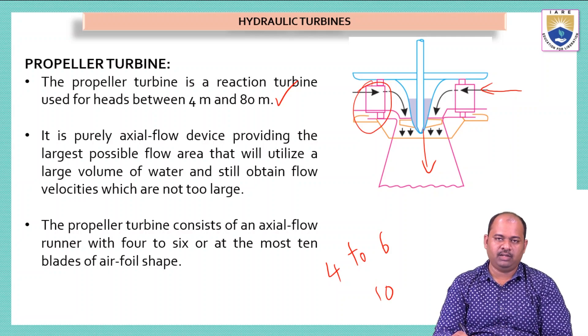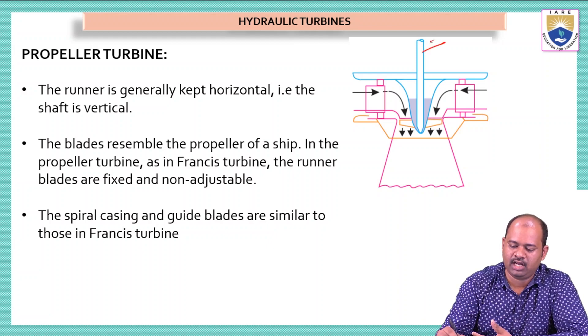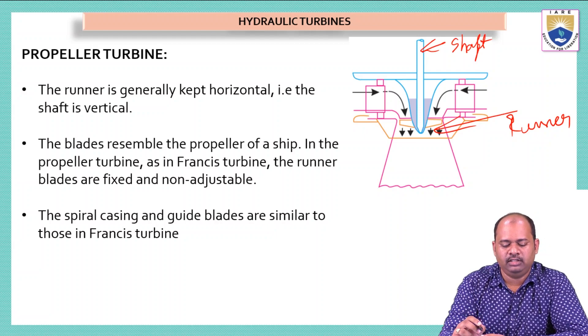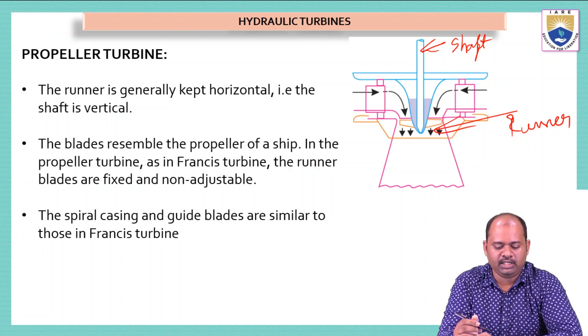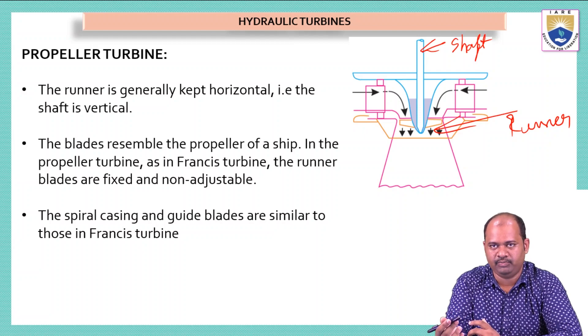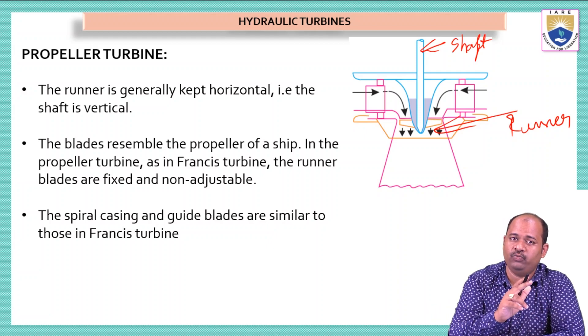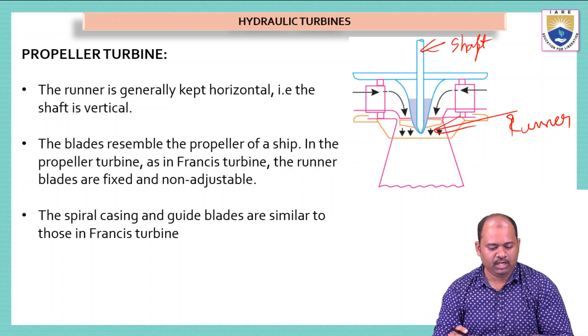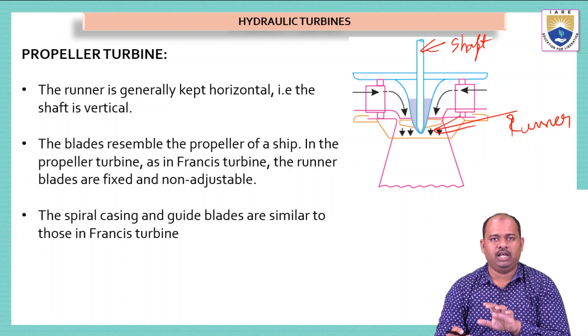The propeller turbine is very similar to the Kaplan turbine, which we will see in the next lecture. The runner is generally kept horizontal with a vertical shaft. The blades resemble the propeller of a ship. In the propeller turbine, as in Francis turbine, the runner blades are fixed and non-adjustable — unlike the guide vanes in Francis turbine which can be adjusted via the governing mechanism. The spiral casing and guide blades are similar to those in Francis turbine.